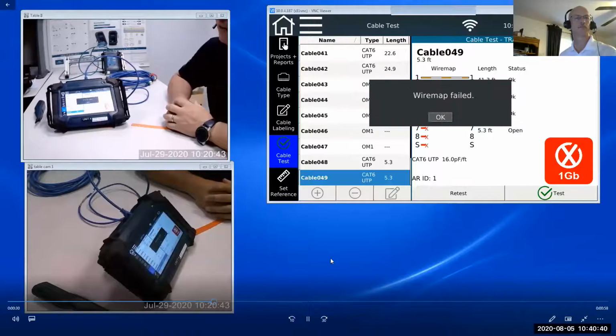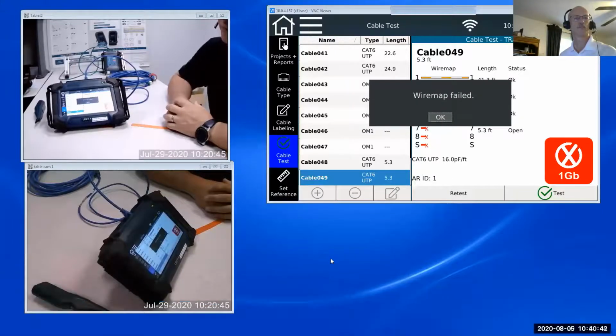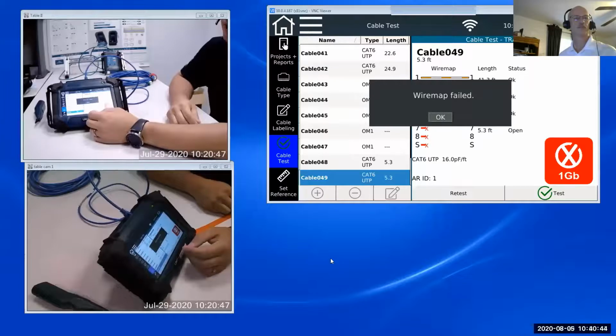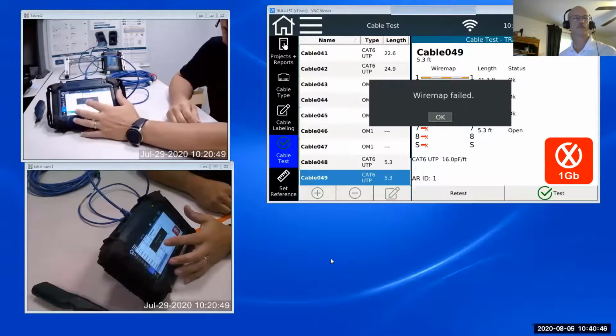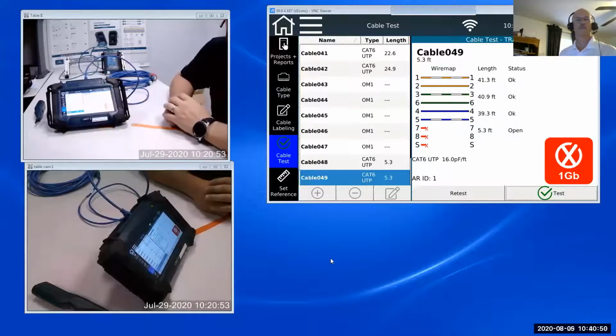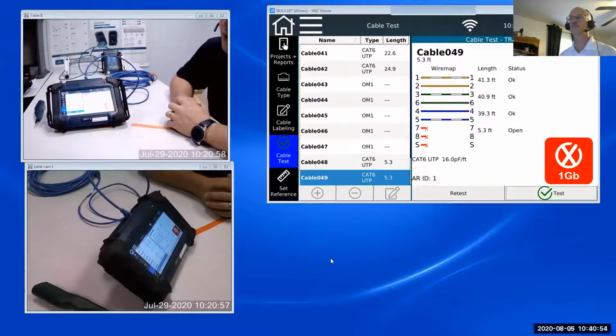Right away, the test fails. It's pretty obvious it's failing the wire map. So what it's telling us here is that the cable is not wired correctly. There's a problem — where is that problem? Well, it's telling us that in this cable assembly, we have pairs 1-2, 3-6, and 4-5 wired correctly. Remember, this is an unshielded cable, so we're not looking for a shield here. But we definitely have a problem with pair 7-8.